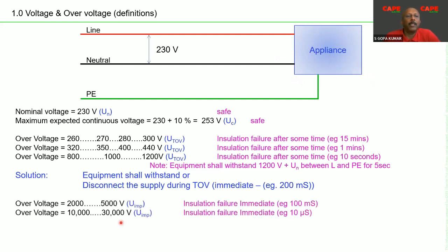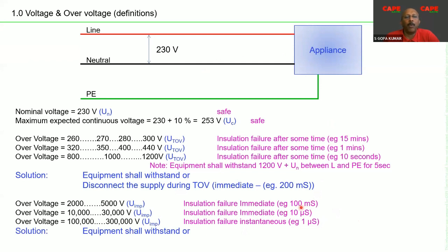Similarly, even higher voltage, let's say in the range of kilovolts, 2 kV, 5 kV, 10,000, 30,000. So once the voltage is more and more, you can see here, it may withstand 100 milliseconds in one case. It may withstand 10 microseconds in one case, and it may withstand 1 microsecond in another case. So depending upon the transient voltage, these are transient voltages. The equipment may be able to withstand for a short time, and immediately after 1 microsecond, for example, it may fail. These are examples I am explaining just to create a background on how SPDs work.